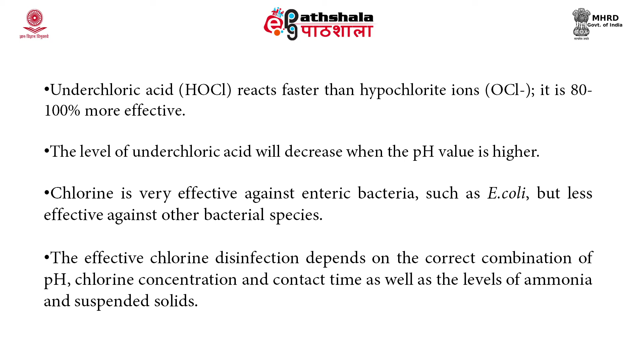The effective chlorine disinfection depends upon the correct combination of pH, chlorine concentration, contact time, as well as the levels of suspended solids and ammonia present in the water. The advantages of this chlorination process of disinfection include that it controls the population of disease causing bacteria.